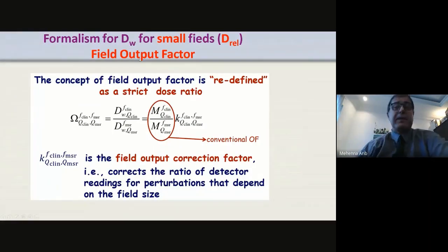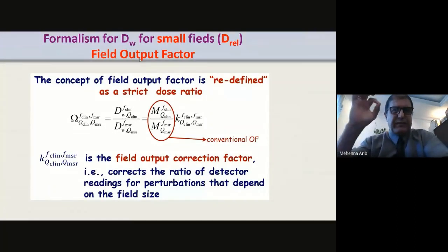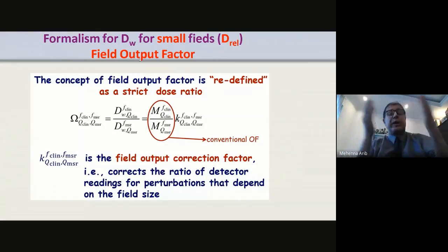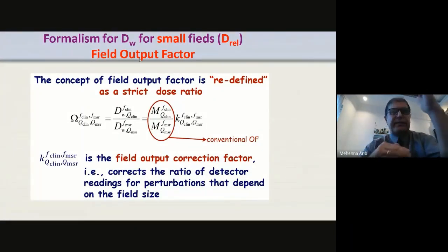calculate. But when you take different detectors, and if you take the ratio of the dose at a given field size divided by the dose at 10 by 10, you will have a problem for the small fields, because the ratio will be completely different, and the difference can be up to 35 or 40%. So if you use the conventional output factor for your calculation, you will have a dose to the patient that is off by more than 30%. So you can have another dosage.